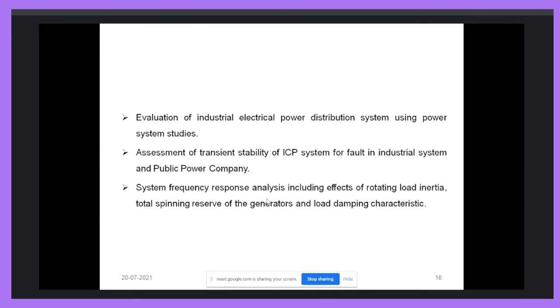So what types of power system studies are basically required for database generation? First and most important is load flow analysis. By load flow analysis for different operating scenarios, we can get data about the generation, load, losses in the system, voltage in the system, branch losses, and power flow in the different branches. All this information we can gather with the help of load flow analysis. We have to perform short circuit analysis so that we can determine what the voltage will be whenever a fault occurs in the system, and what the frequency will be.